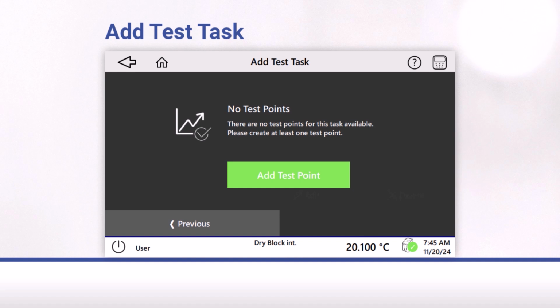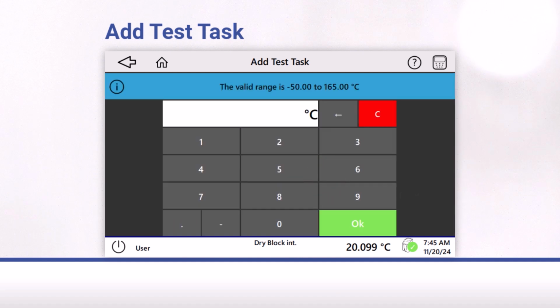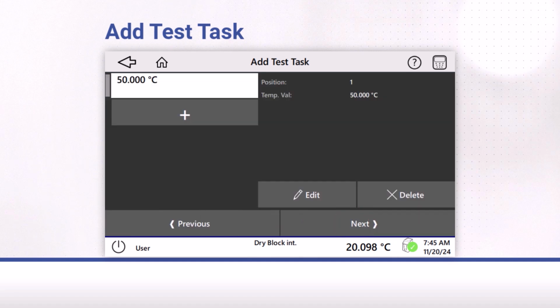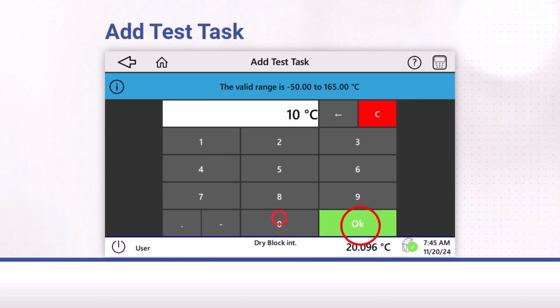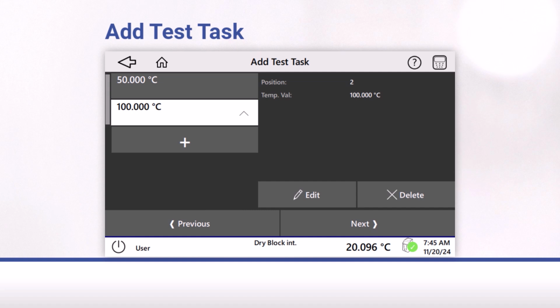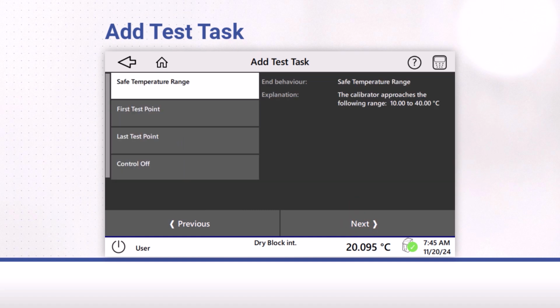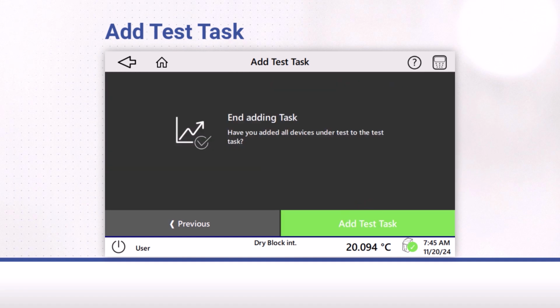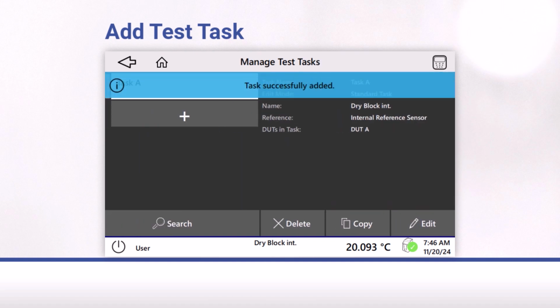Tap Add Test Point. Enter the test point. You can add more test points, edit or delete existing test points, or change the order of the test points. Select the behavior of the temperature calibrator at the end of the calibration. Tap Add Test Task. Your test task has been successfully added.